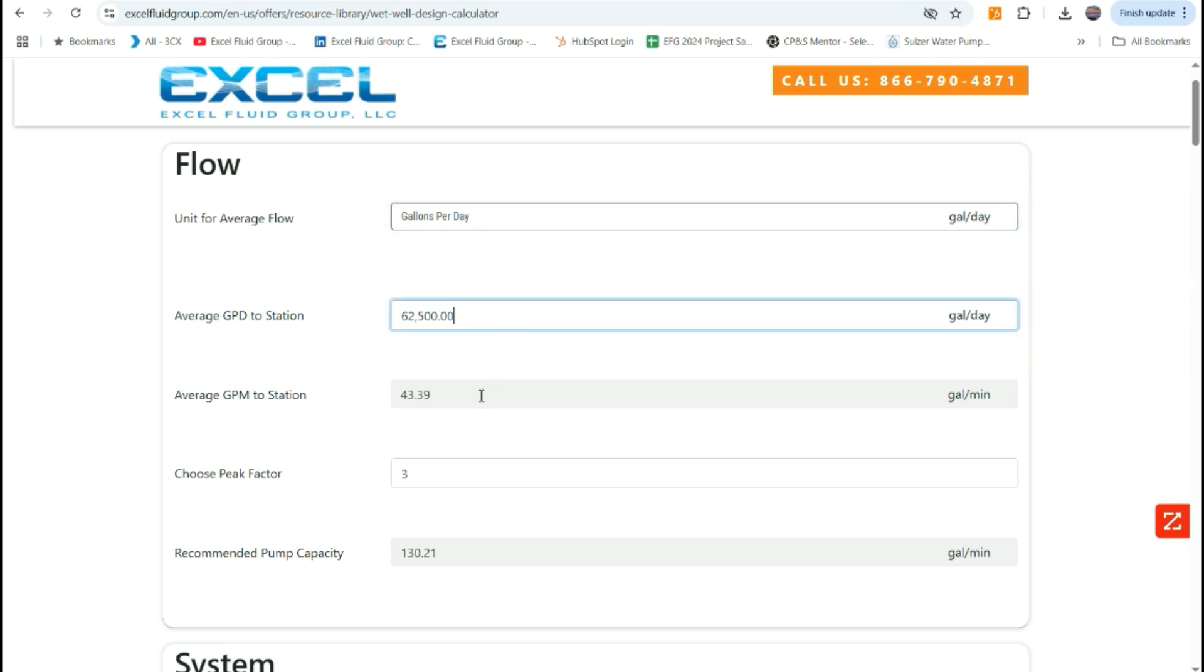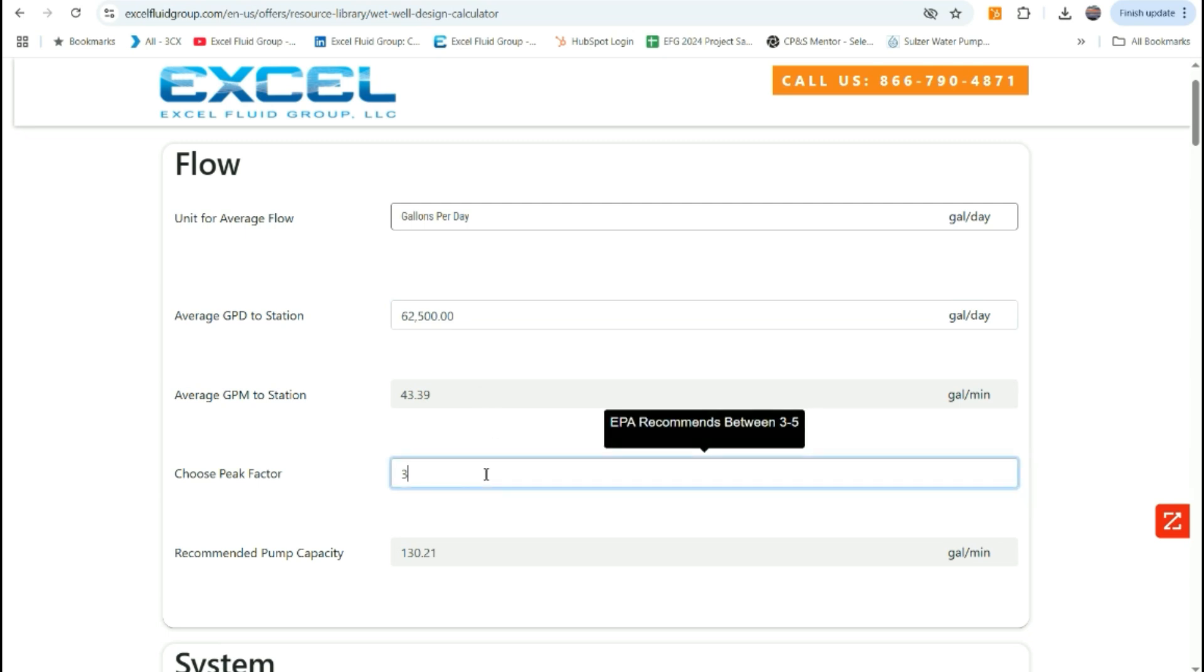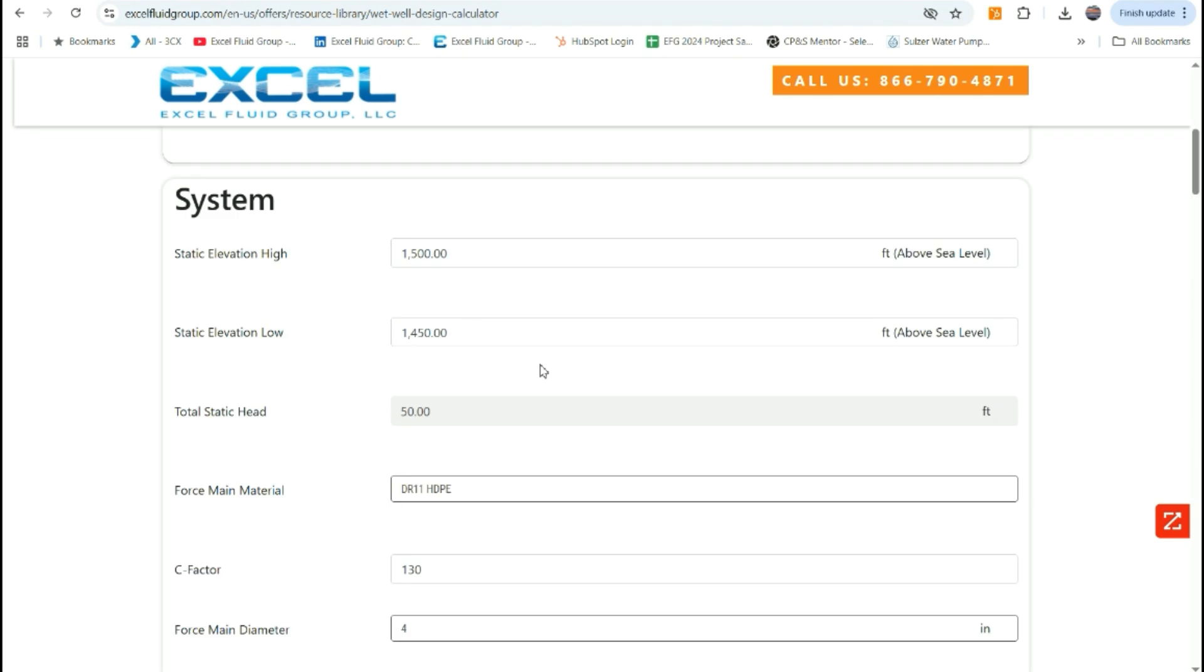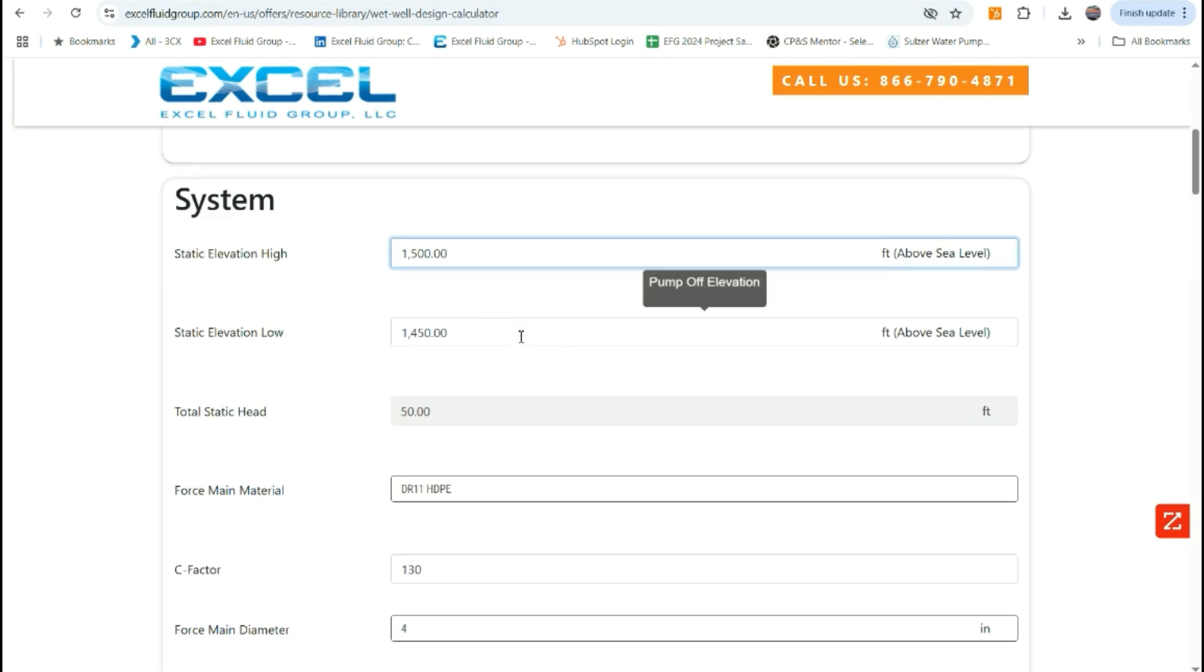The other input we need in this section is the peak factor for the station. EPA recommends between 3 and 5, but the calculator is not limited to that range. The combination of the average flow and the peak factor will provide a recommended pump capacity. Once your flow capacity has been calculated, then you can move on to the system curve section.